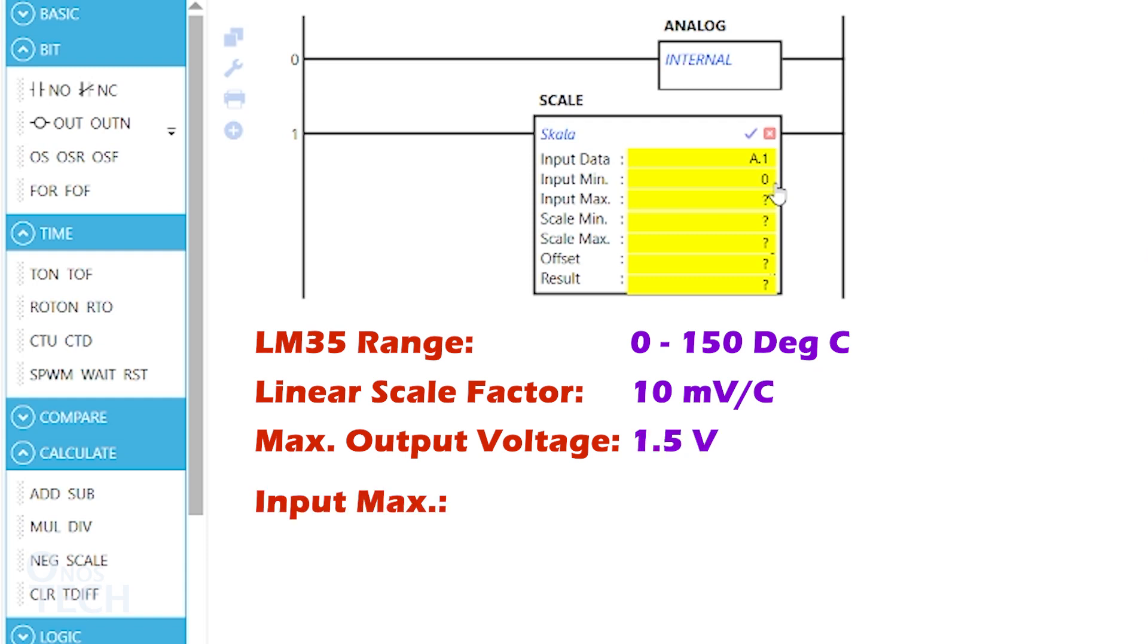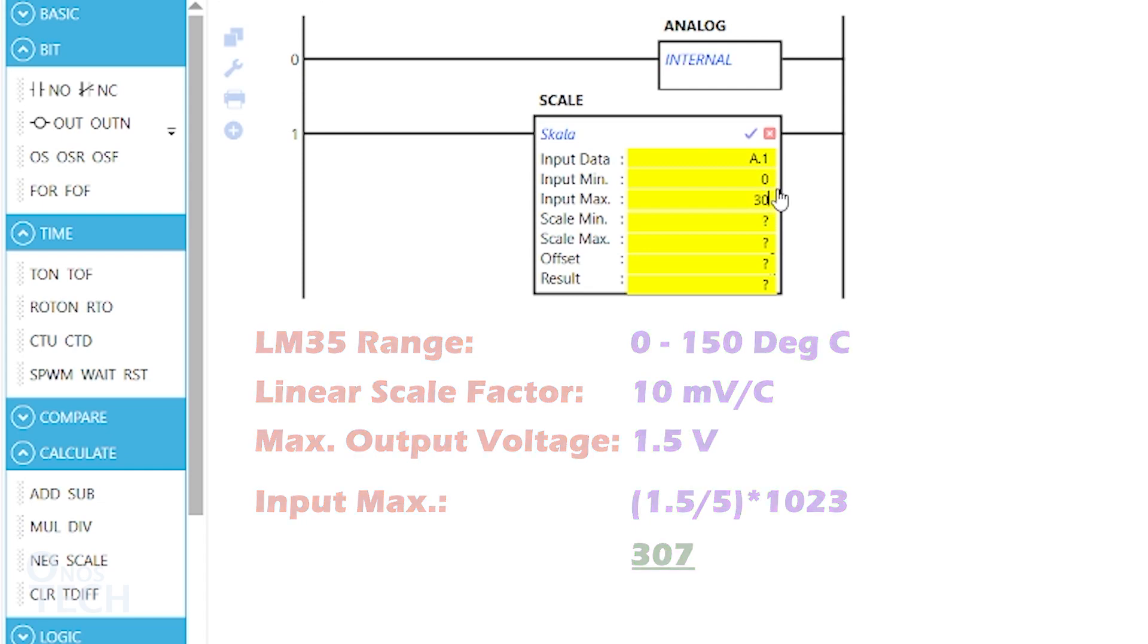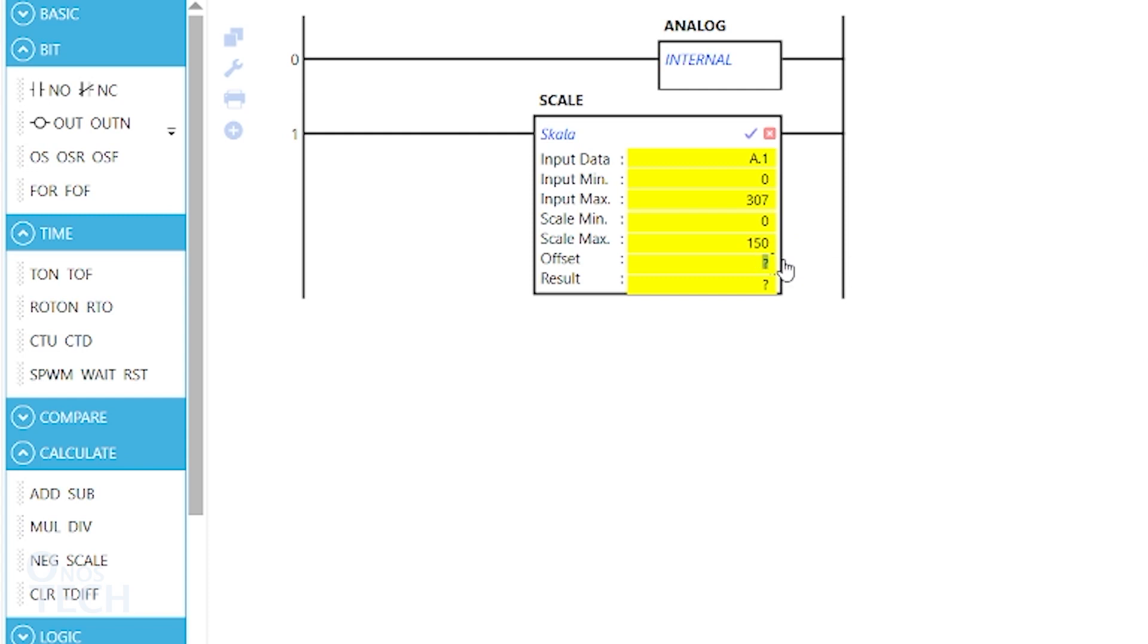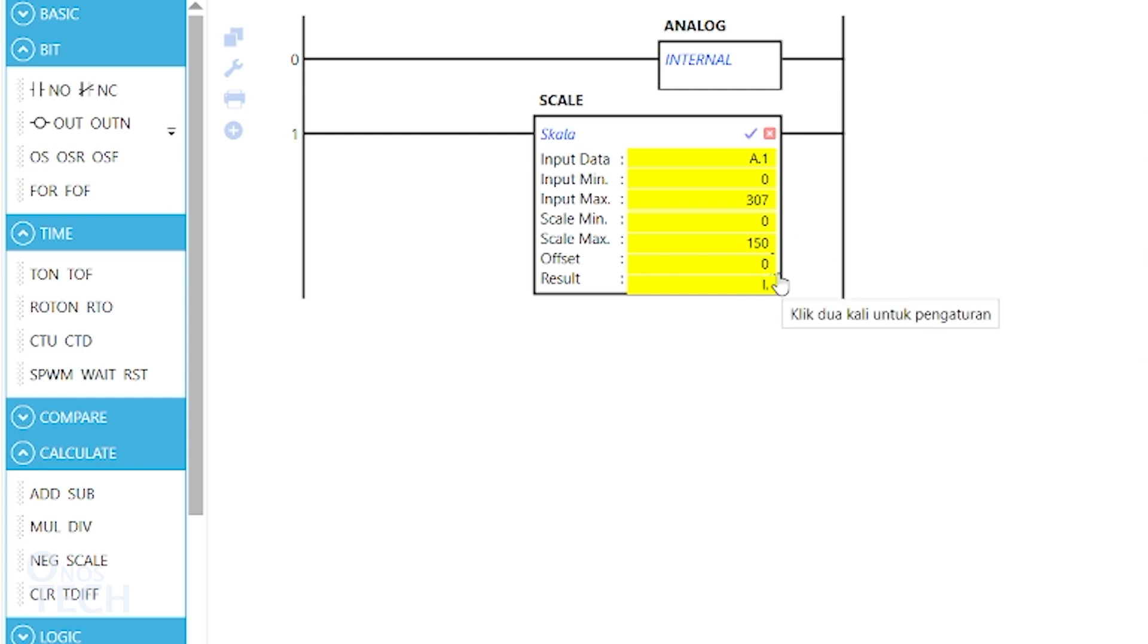Therefore, the input maximum will be 1.5 divided by 5 multiplied by 1023, which approximates to 307. Set the scale minimum to 0, the scale maximum to 150, offset to 0, and the result to I.1.